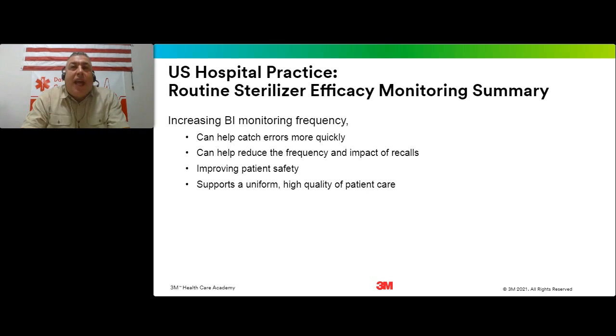We have the capability - we shouldn't be releasing goods that are that hot. You're going to need more than 24 minutes for a cart to cool down. So theoretically, we are quarantining anything before that BI is read, because it has to cool down. So if you're not on any kind of rapid technology, that's another reason to consider it, because you essentially have the ability to almost quarantine everything.